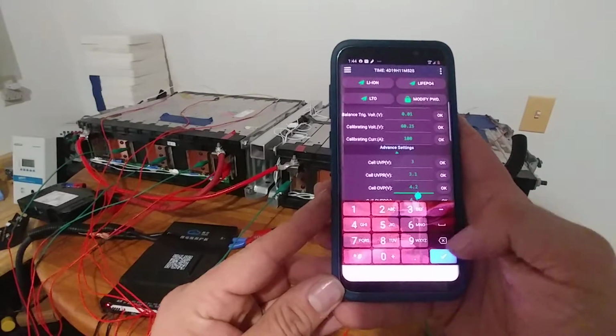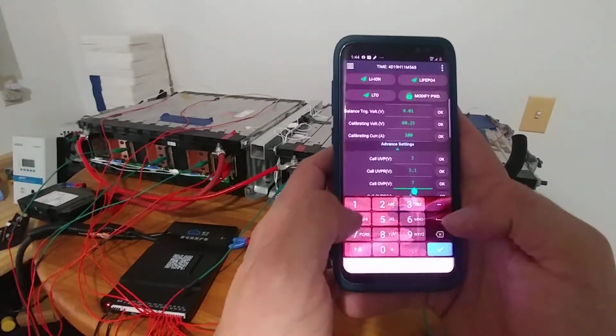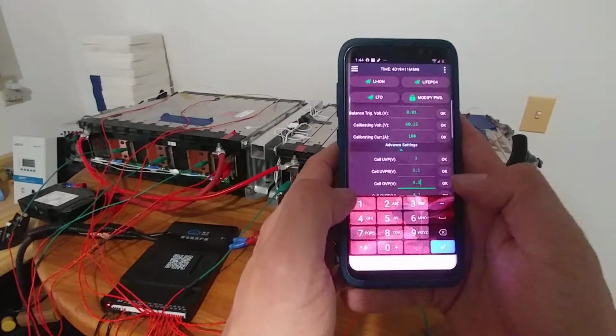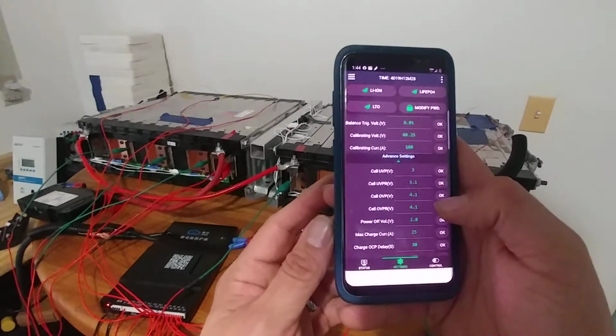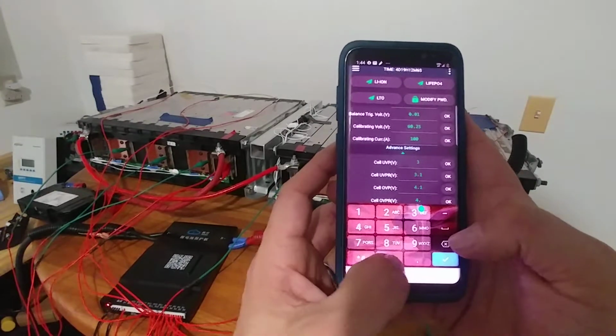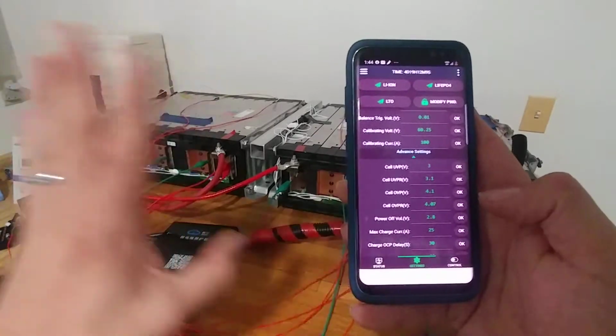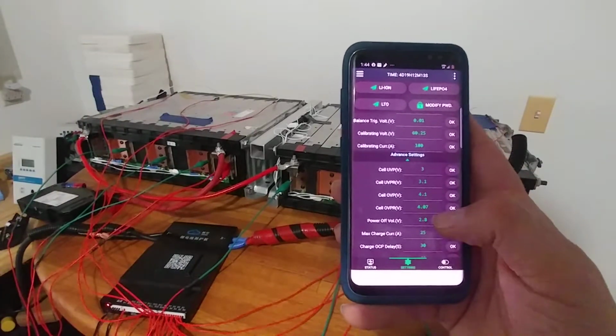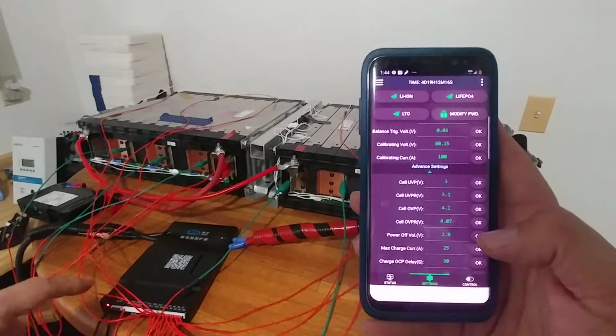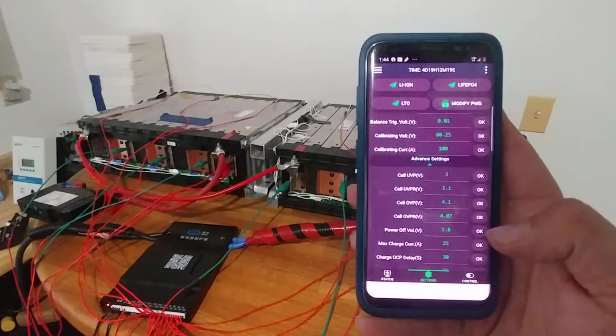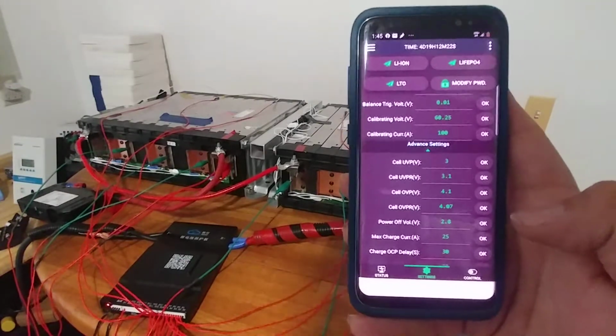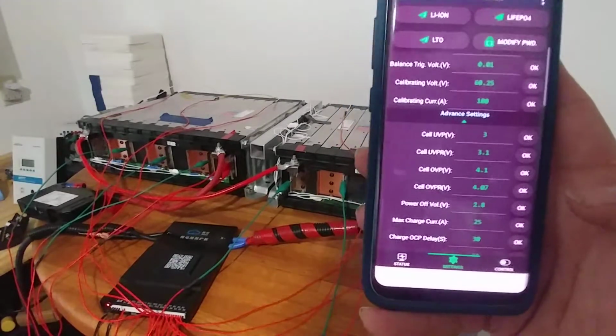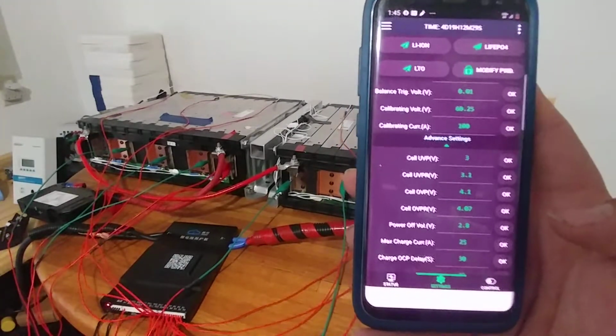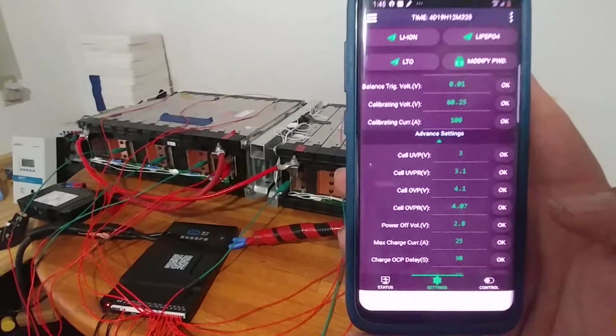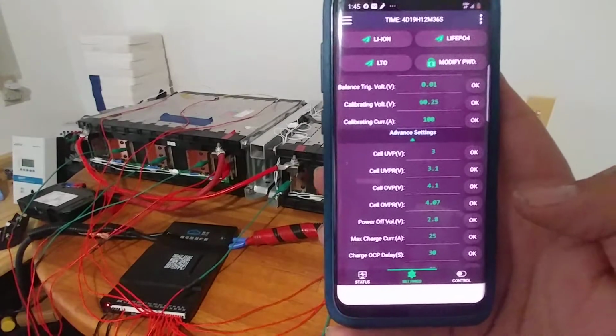So for this one right here, the over voltage protection is going to be 4.1. And you see it failed because they're the same value. So I have to set the recovery to 4.07. And now everything is appropriate. The power off voltage is the voltage at which this little light's going to turn off and the BMS is going to stop functioning, because the BMS actually does draw a small amount of power. And if you were to just leave this battery alone for months on end, eventually this BMS would drain it down below the threshold voltage, which is why we have the ability to use a secondary battery to wake this thing up again.